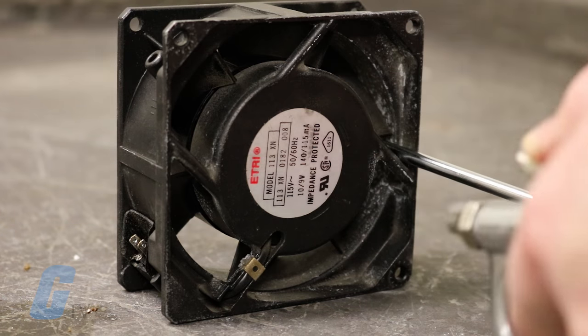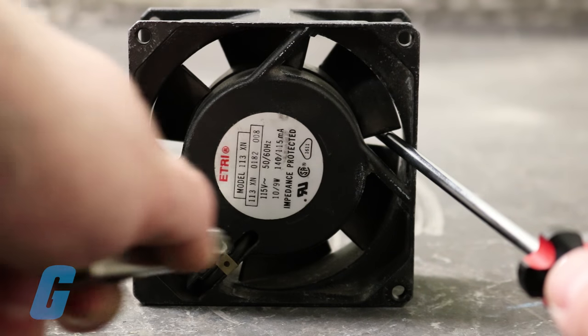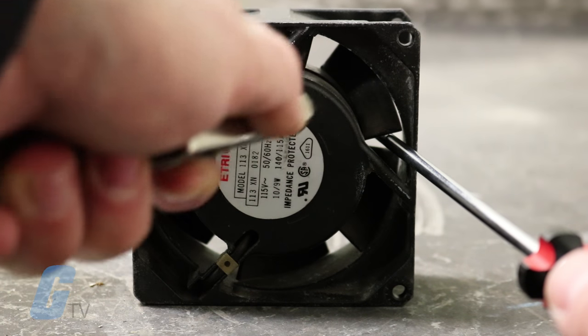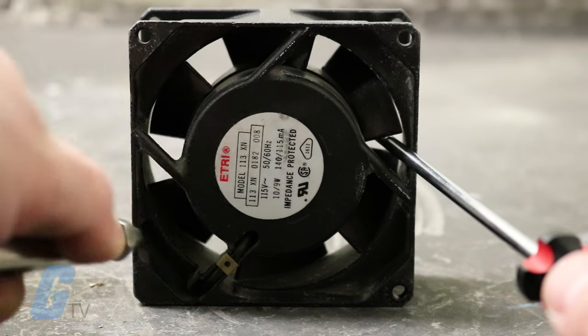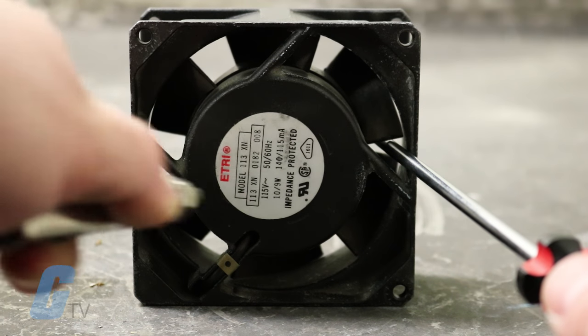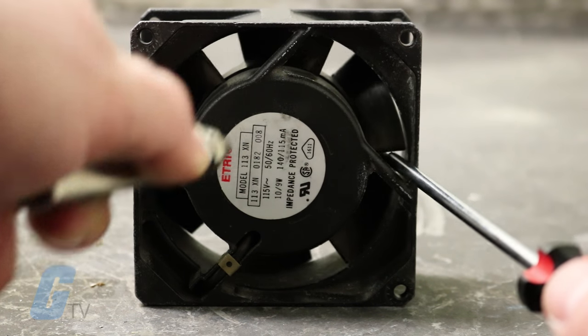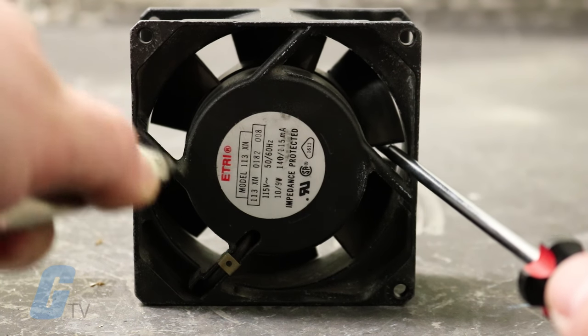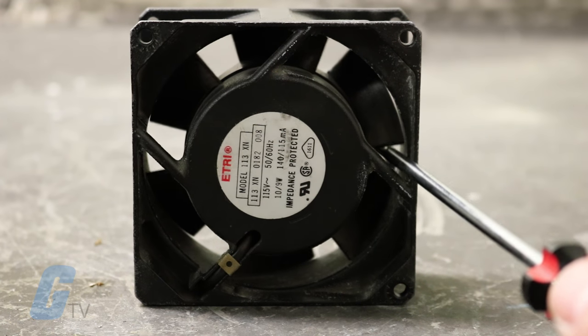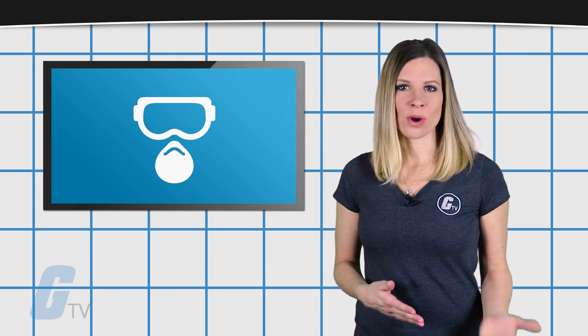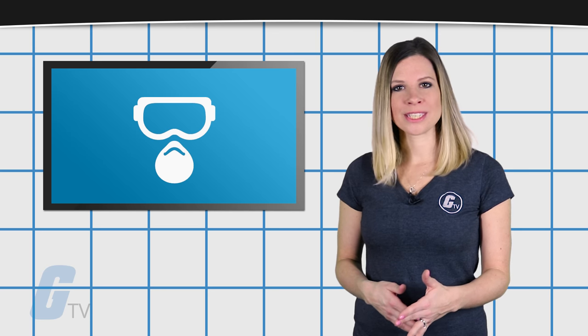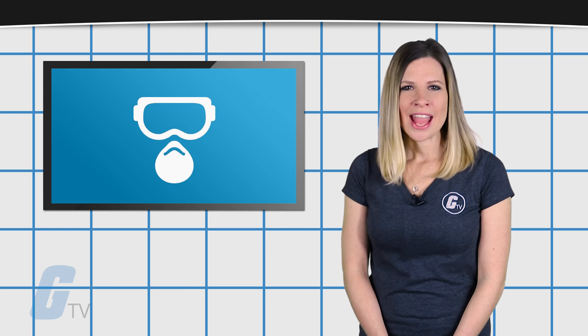You will want to use a small tool such as a screwdriver to hold the fan blades in place while blowing out the contaminants, as fans can be damaged due to over-speeding from the high velocity compressed air. We also recommend wearing a dust mask or goggles for protection while doing so.